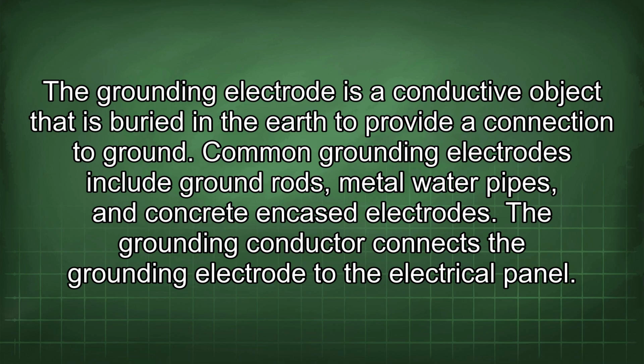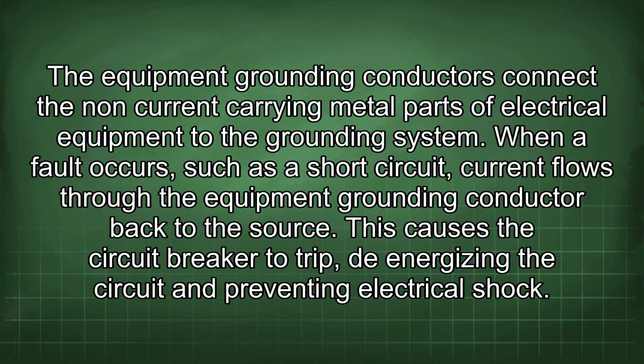The grounding conductor connects the grounding electrode to the electrical panel. The equipment grounding conductors connect the non-current carrying metal parts of electrical equipment to the grounding system. When a fault occurs, such as a short circuit, current flows through the equipment grounding conductor back to the source. This causes the circuit breaker to trip, de-energizing the circuit and preventing electrical shock.